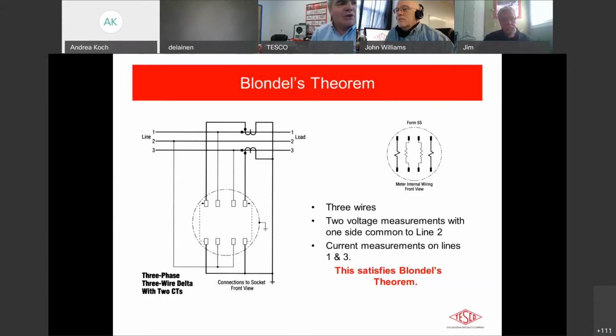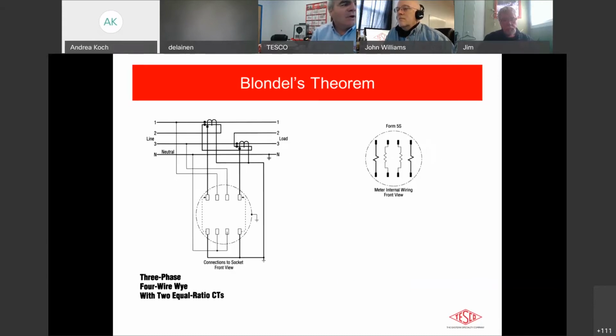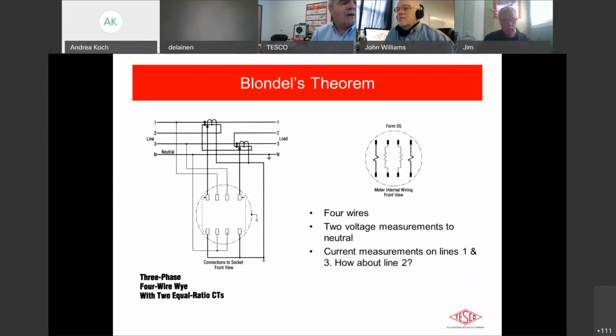So everything is good here. Go ahead. Now we've got a 3-phase, 4-wire Y system with 2 equal ratio CTs. So very similar. We're using the same meter. We're using that same 5S. But now we are not meeting Blondel's theorem. We are not accurately metering this service.